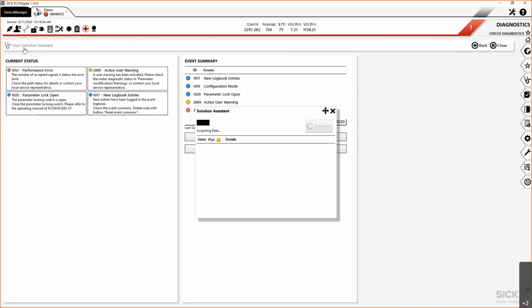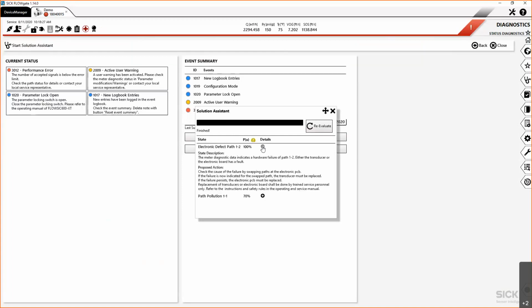You can click on that and the solution assistant goes through some fuzzy logic. This is to help assist the technician out in the field to try to determine what might be wrong with the meter. You see here, if I click on this, it says there's a 100% chance that there's an electronic defect. If you click on this, the state of the diagnostic data indicates a hardware failure: either the transducer or the electronics board has a fault. Then it goes through some proposed actions to correct that. Again, this is to assist the technician out in the field to try to determine what the problem might be.